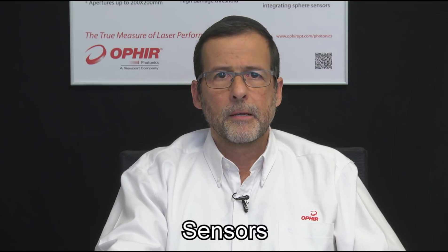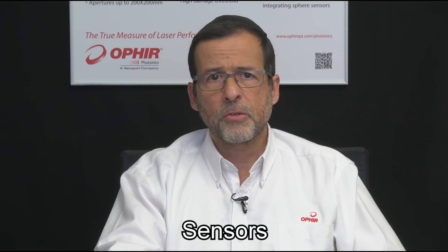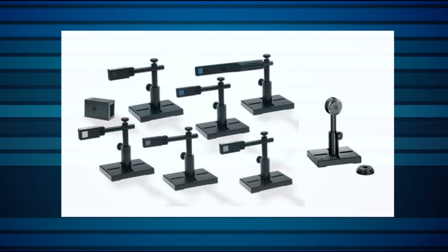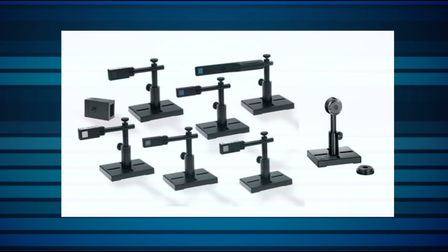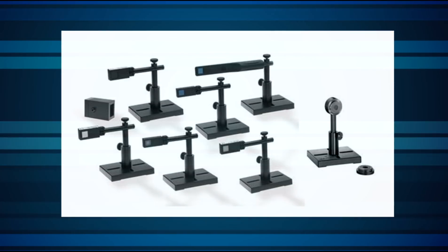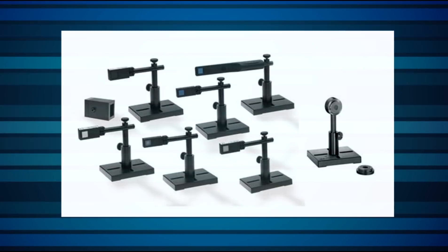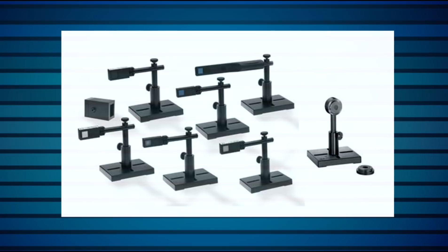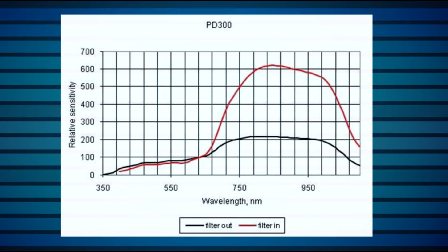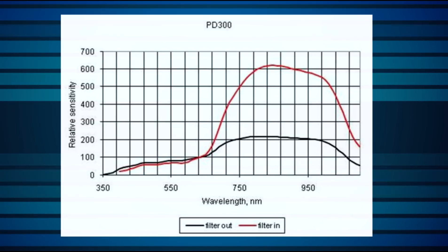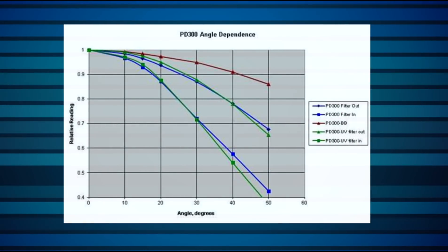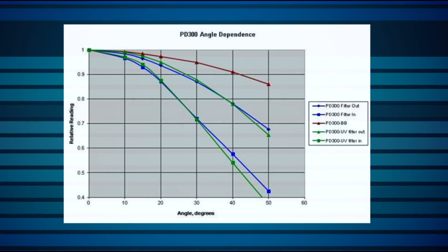Measurements of this sort usually make use of a photodiode-based sensor, suitably calibrated and stabilized, with various semiconductor materials used for various spectral regions. A photodiode is fast and sensitive. However, its spectral response is narrow and not at all flat. Also, there is some sensitivity to incidence angle and to temperature.